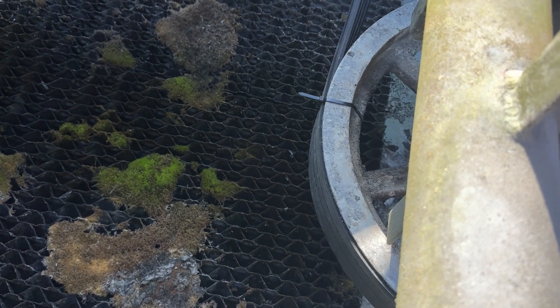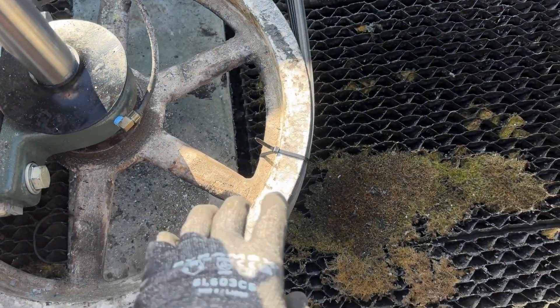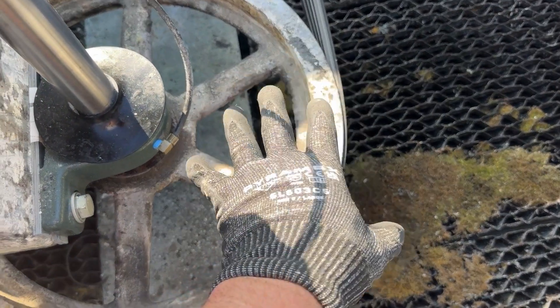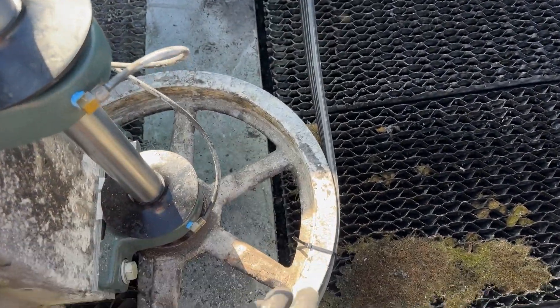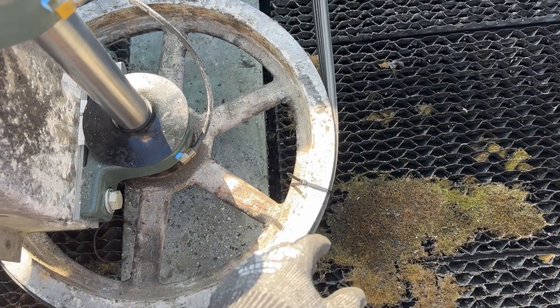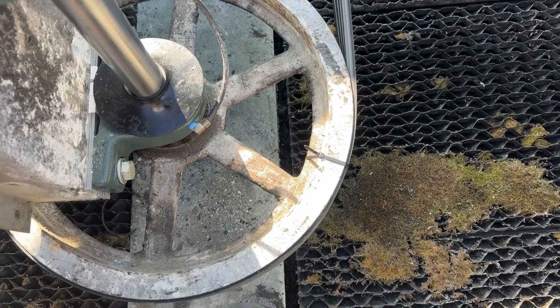Getting ready to set the fan belt now. Before I do that, I'm just going to put some zip ties on this belt to hold it on this pulley. Then when I go and put it on the motor pulley, these will just snap off. This is a good way to get the belt on here if you're working by yourself.